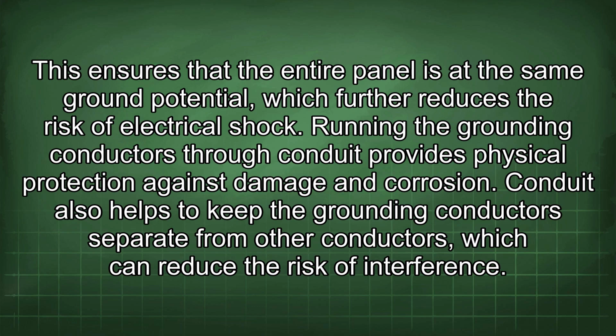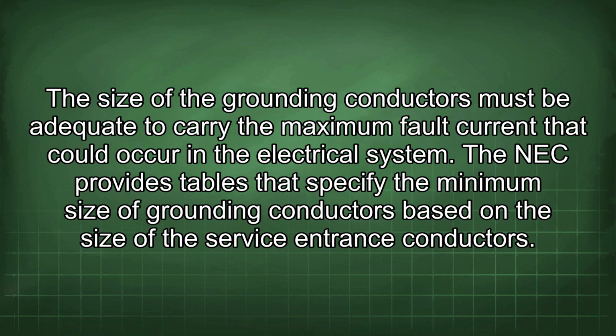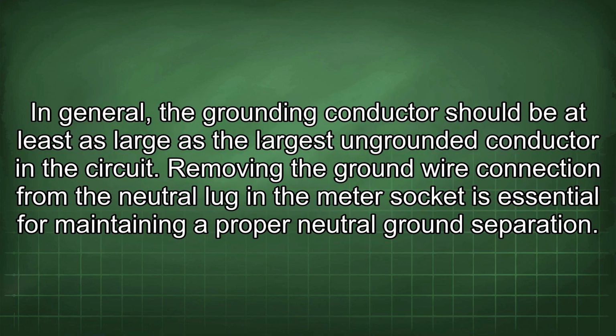Running the grounding conductors through conduit provides physical protection against damage and corrosion. Conduit also helps to keep the grounding conductors separate from other conductors, which can reduce the risk of interference. The size of the grounding conductors must be adequate to carry the maximum fault current that could occur in the electrical system. The NEC provides tables that specify the minimum size of grounding conductors based on the size of the service entrance conductors. In general, the grounding conductor should be at least as large as the largest ungrounded conductor in the circuit.